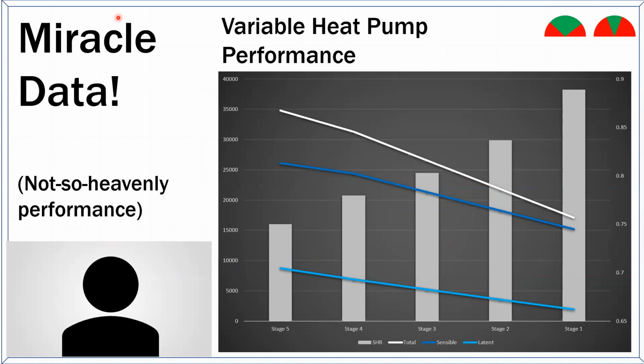Compressors are expensive to run and fans are cheap to run. And so if I chose to design my new inverter system or multi-stage system to squeeze a little more energy out of the unit by running a faster fan, so that the reduction in power went down on the compressor faster than it went down on the fan...